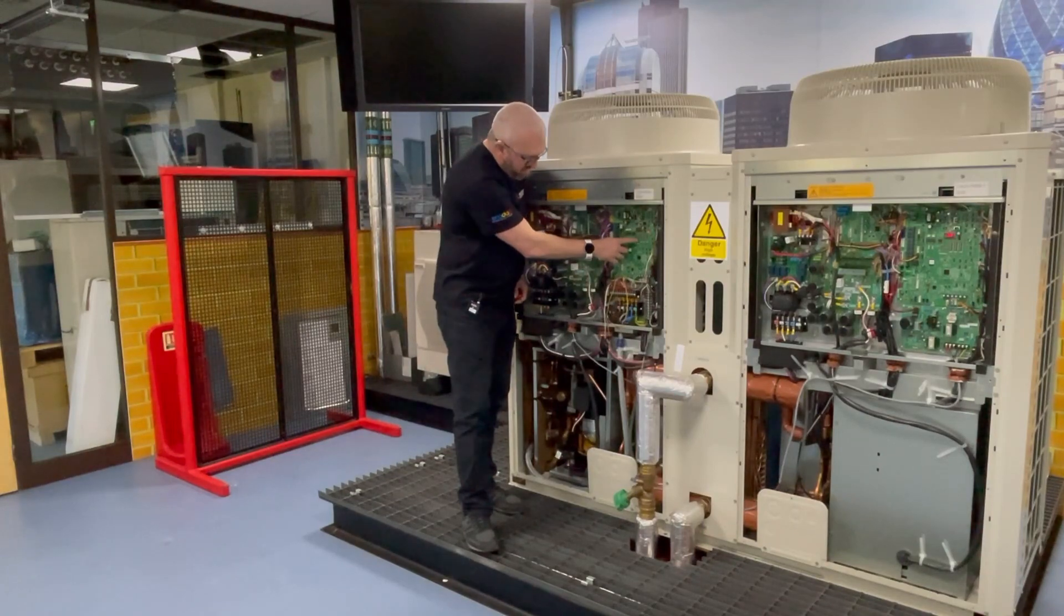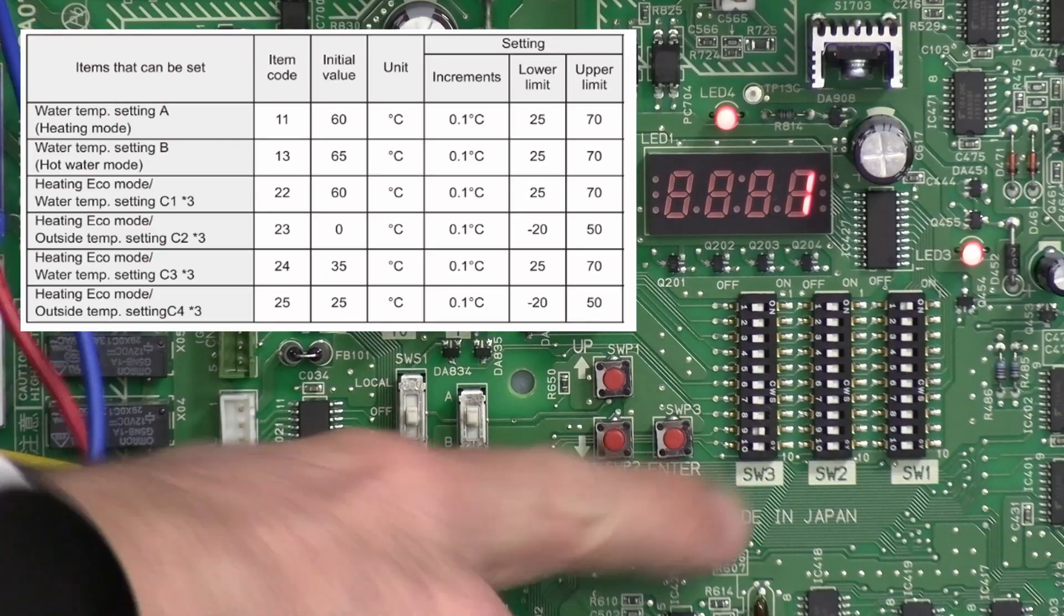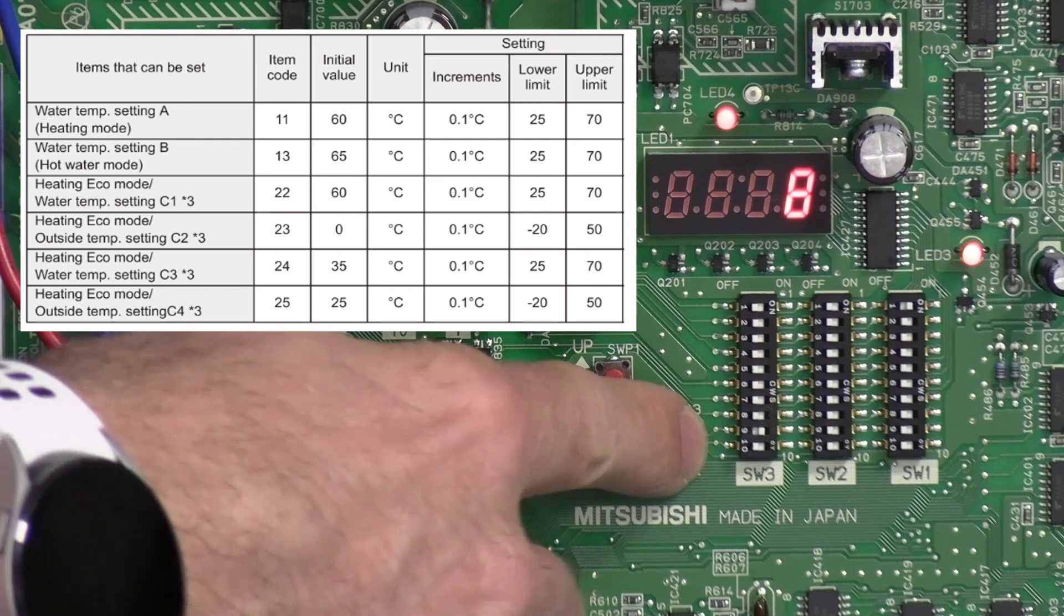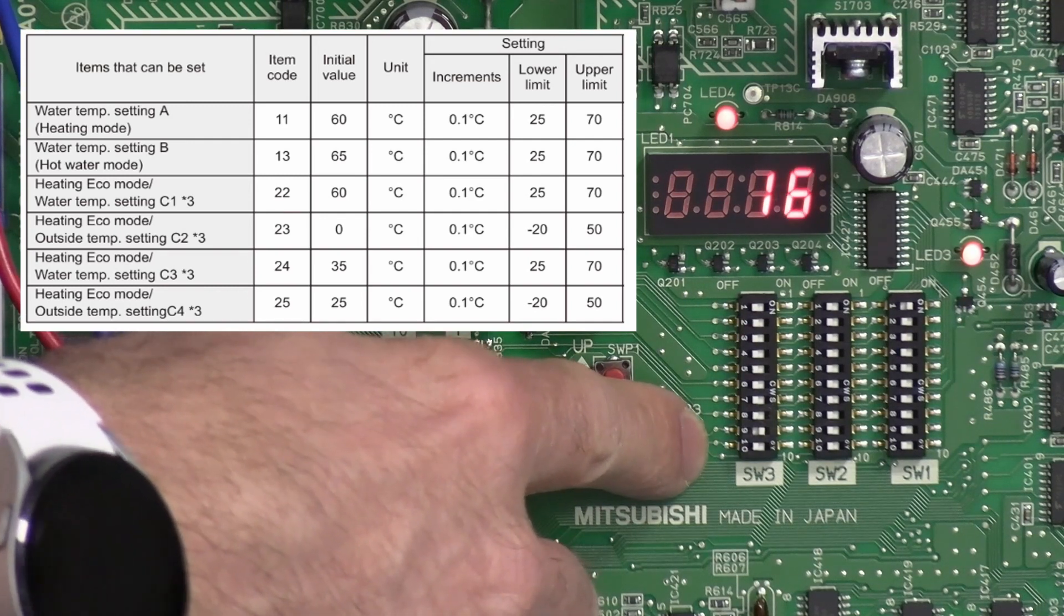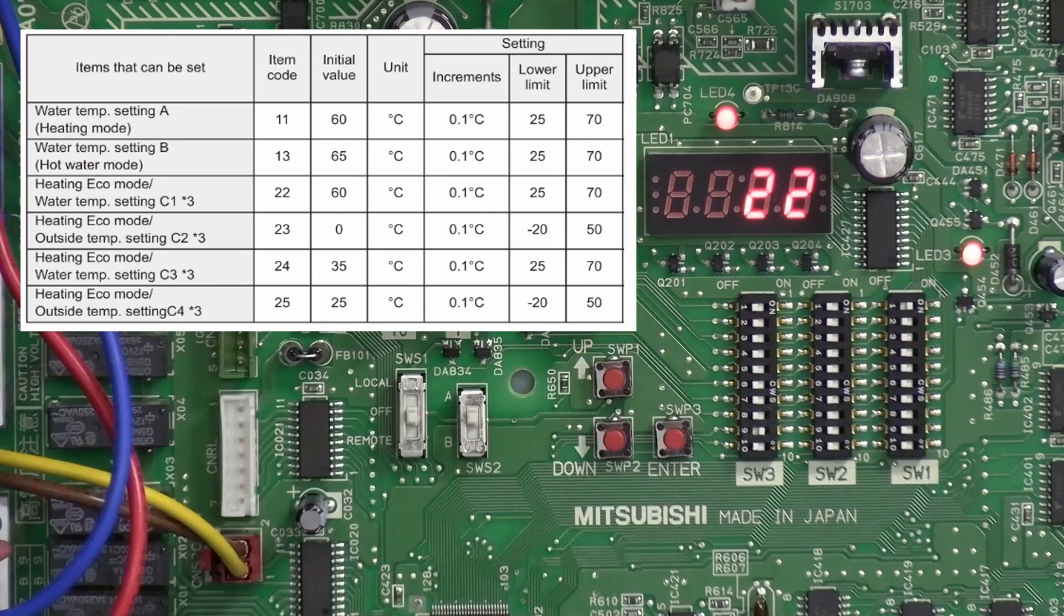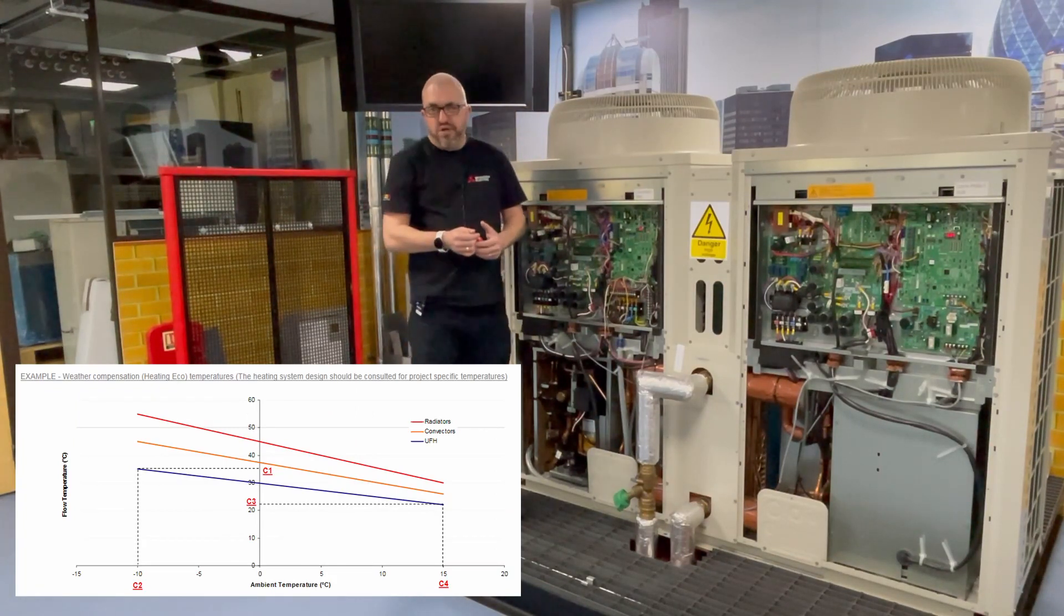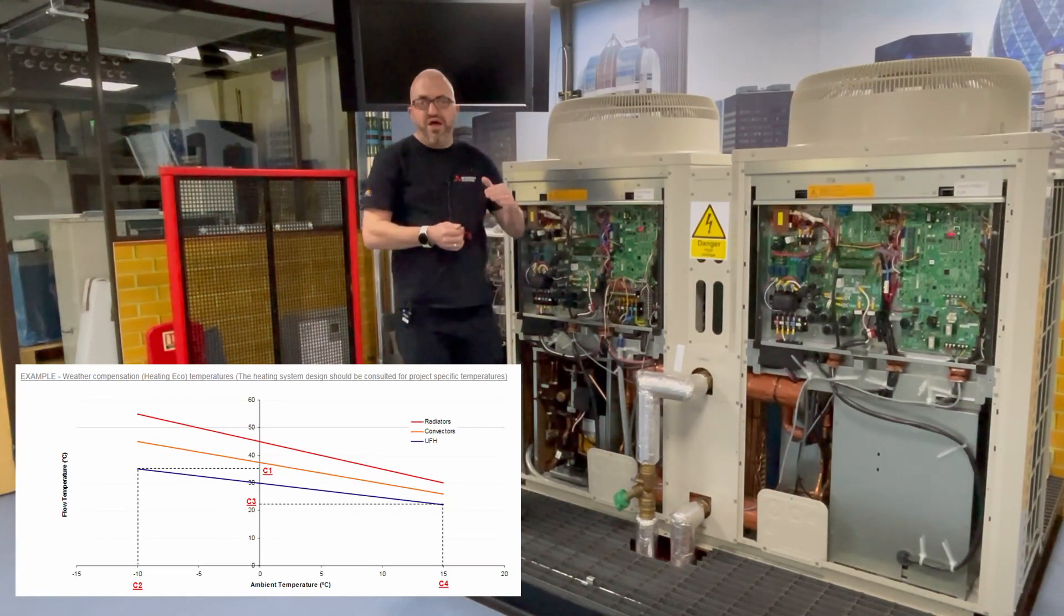We're now going to use a select switch here, and each time you press it it moves through the operation numbers. Now the first one we want is item 22, so 22 is going to be our high end of the scale, the highest flow temperature the system will aim for.